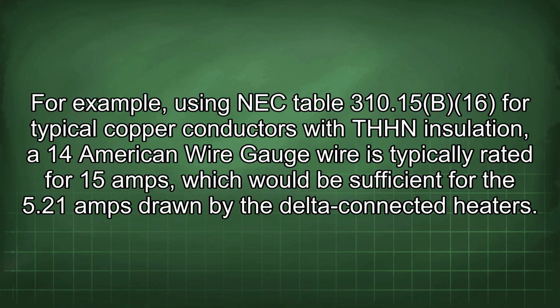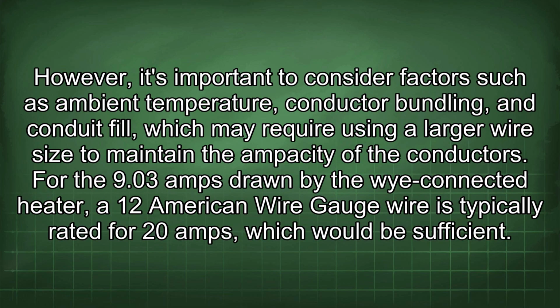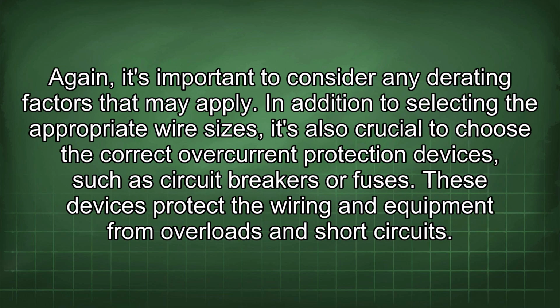For example, using NEC table 310.15(B)(16) for typical copper conductors with THHN insulation, a 14 American wire gauge wire is typically rated for 15 amps, which would be sufficient for the 5.21 amps drawn by the Delta connected heaters. However, it's important to consider factors such as ambient temperature, conductor bundling, and conduit fill, which may require using a larger wire size to maintain the ampacity of the conductors. For the 9.03 amps drawn by the Y-connected heater, a 12 American wire gauge wire is typically rated for 20 amps, which would be sufficient. Again, it's important to consider any derating factors that may apply.